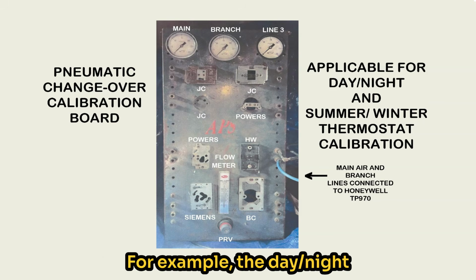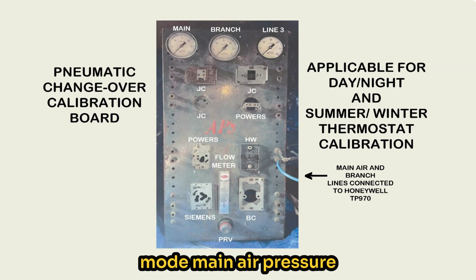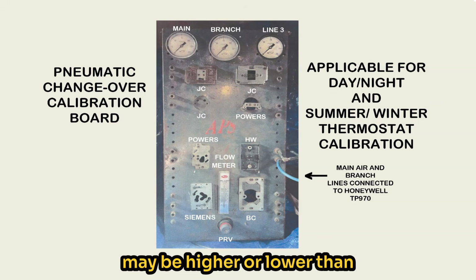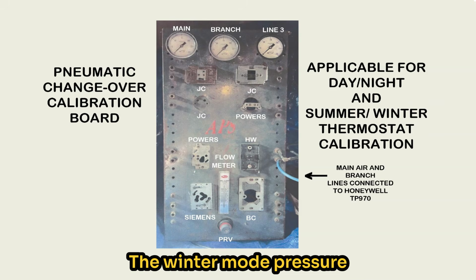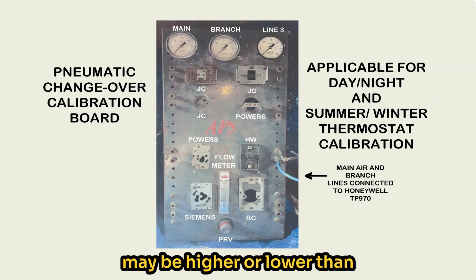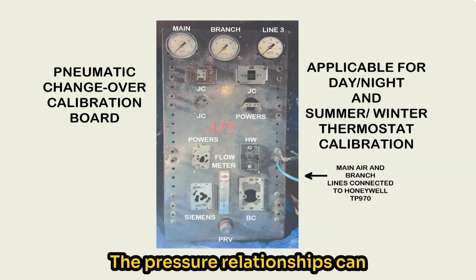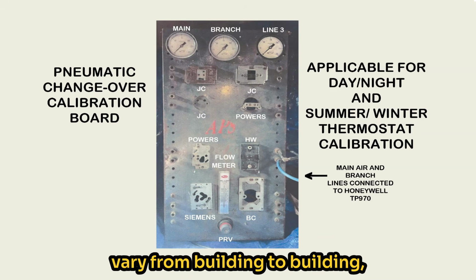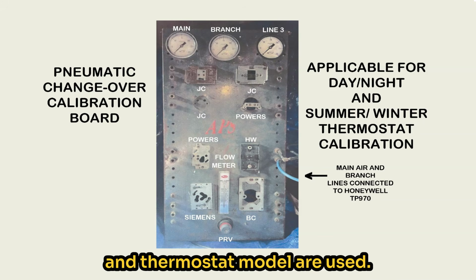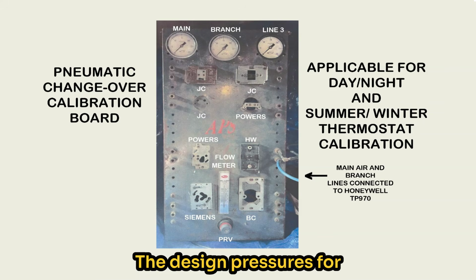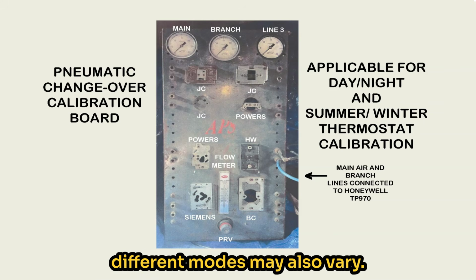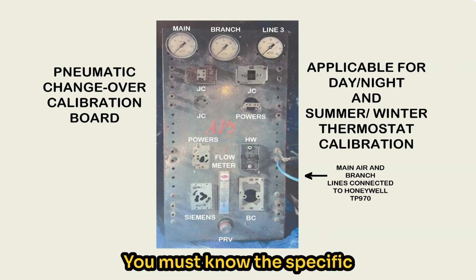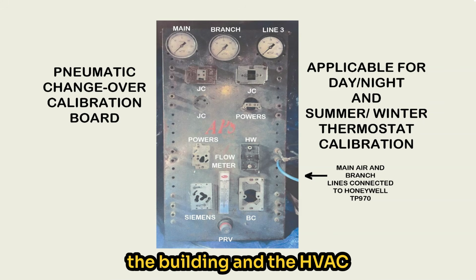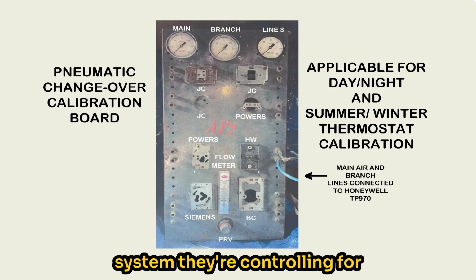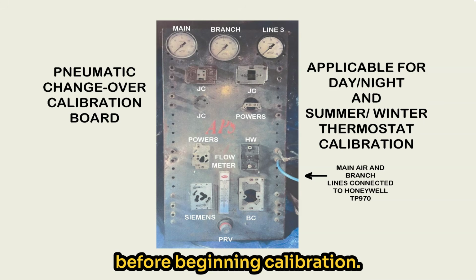For example, the day-night mode main air pressure may be higher or lower than the night mode pressure. The winter mode pressure may be higher or lower than the summer mode pressure. The pressure relationships can vary from building to building, even when the same manufacturer and thermostat model are used. The design pressures for different modes may also vary. You must know the specific operating requirements of the building and the HVAC system they're controlling for before beginning calibration.